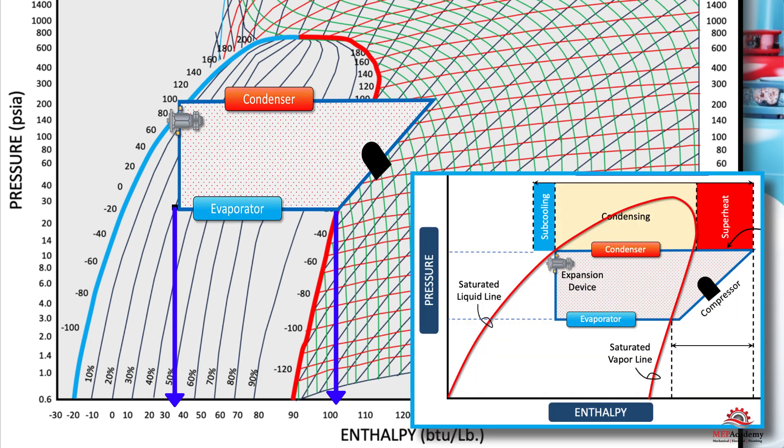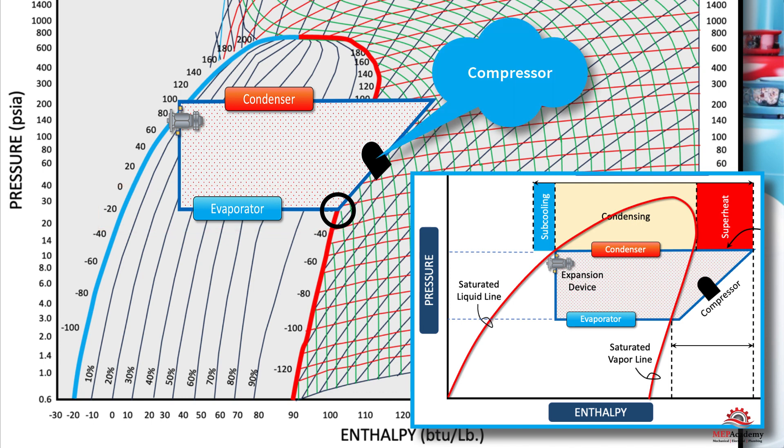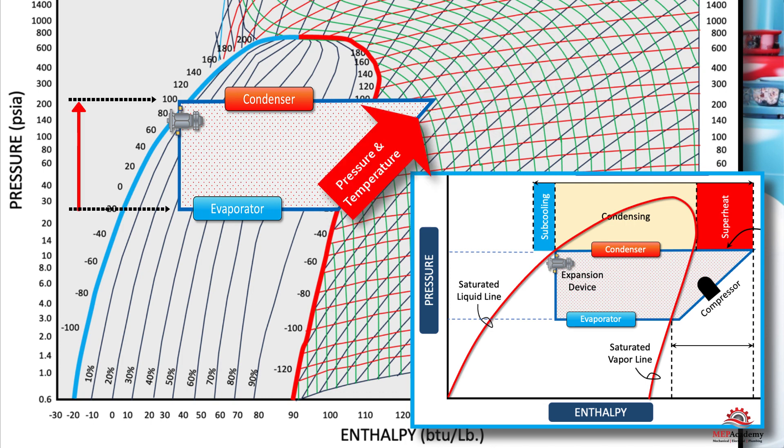The constant temperature and pressure line is where the evaporator turns liquid refrigerant into vapor. When it reaches the saturated vapor line, it should be 100% vapor, as this is where it will enter the compressor, which works only with vapor. The compressor will raise the pressure and temperature up to the condensing temperature and pressure.